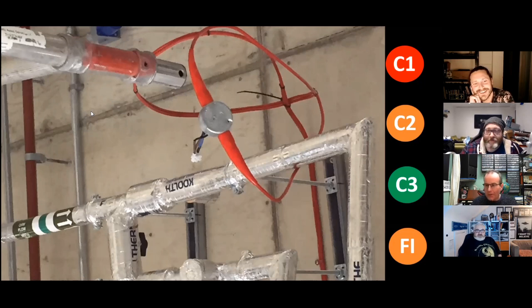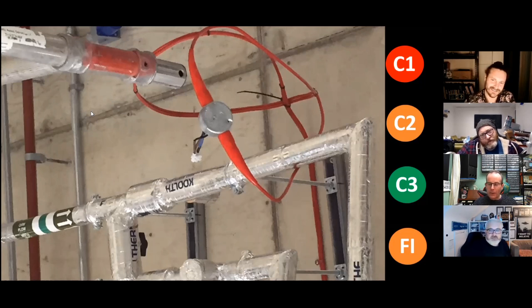I mean, also in the back there, there's a plastic cable tie trying to hold it together and they haven't even cut the tail off the end of it. It's all just thrown in and lashed together. So are we thinking that this is a temporary termination for testing and we haven't come back to it? Yeah, it looks like it was taken from the floor where there's an access tower. You can see the top of it protruding. You can see the unistruts on the ceiling, the pipe work, what looks like a sprinkler hose and a fire main.